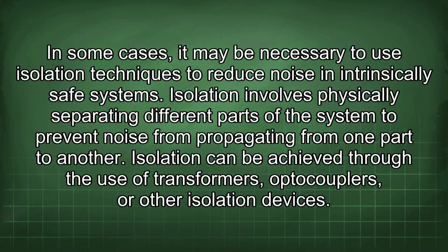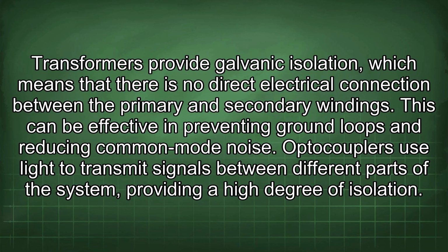In some cases, it may be necessary to use isolation techniques to reduce noise in intrinsically safe systems. Isolation involves physically separating different parts of the system to prevent noise from propagating from one part to another. Isolation can be achieved through the use of transformers, optocouplers, or other isolation devices. Transformers provide galvanic isolation, which means that there is no direct electrical connection between the primary and secondary windings.